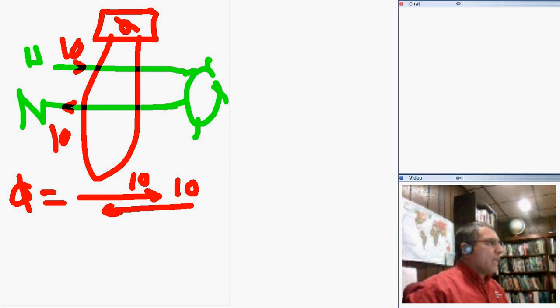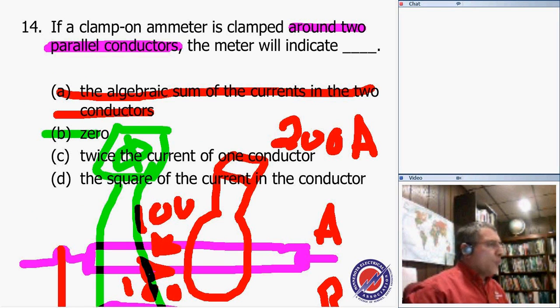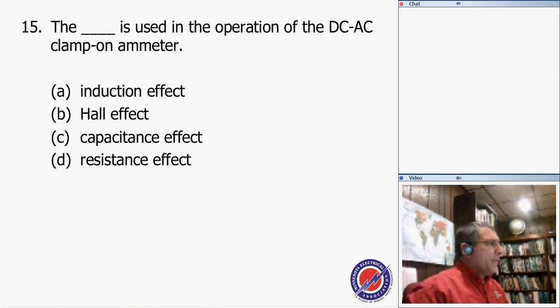So you can measure it across one phase, not two phases, not three phases, not a phase and a neutral, across one phase at a time. Number 15 is on the operation of a DC/AC clamp-on ammeter. If you have a DC/AC clamp-on ammeter, number 15 is B, the Hall effect, and you can get that one directly from the book.